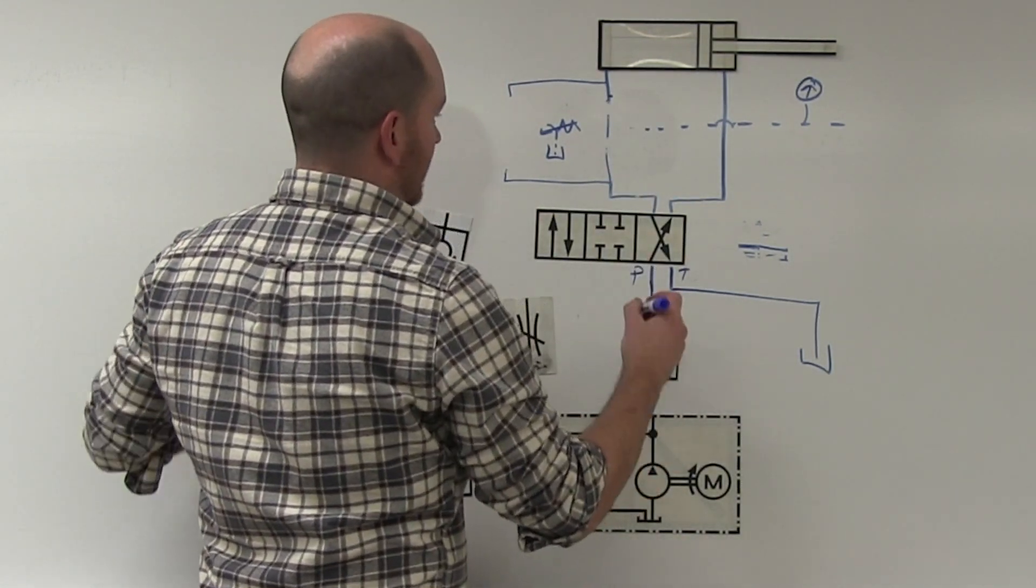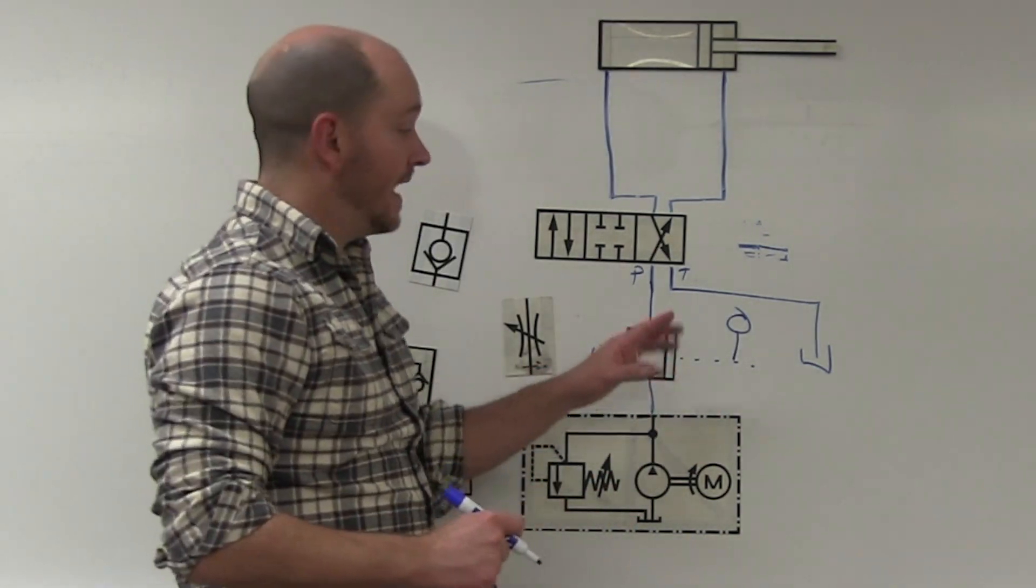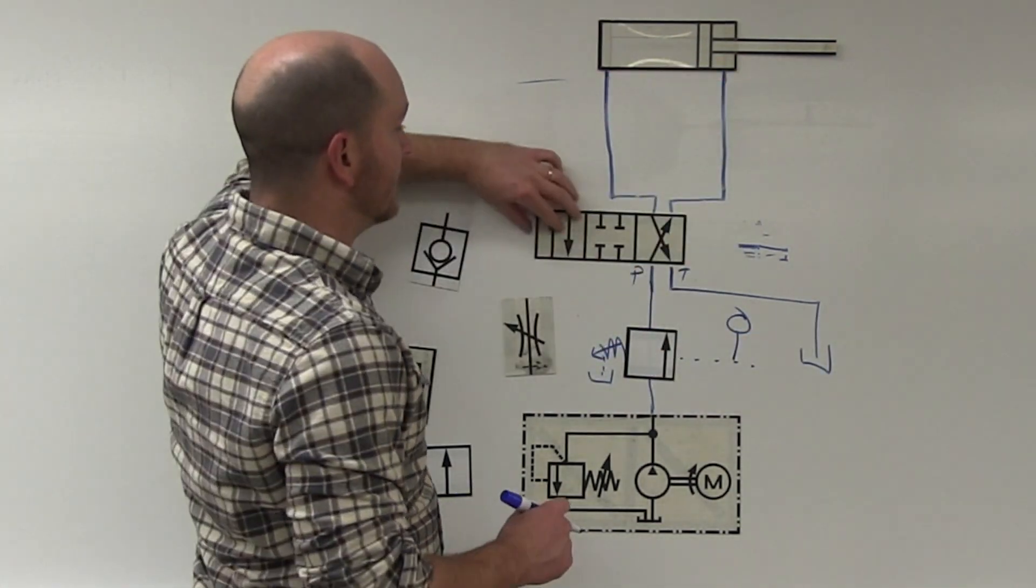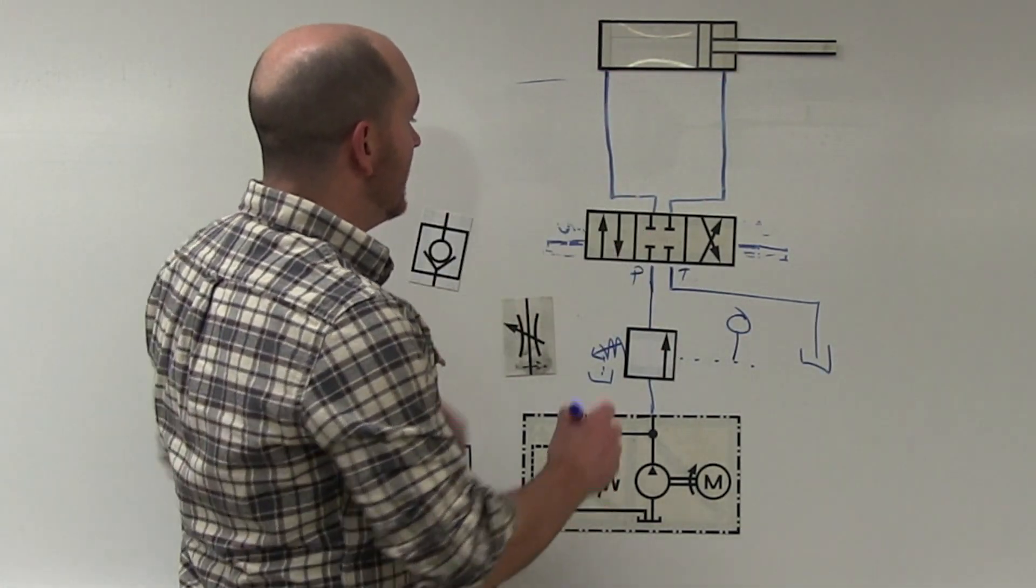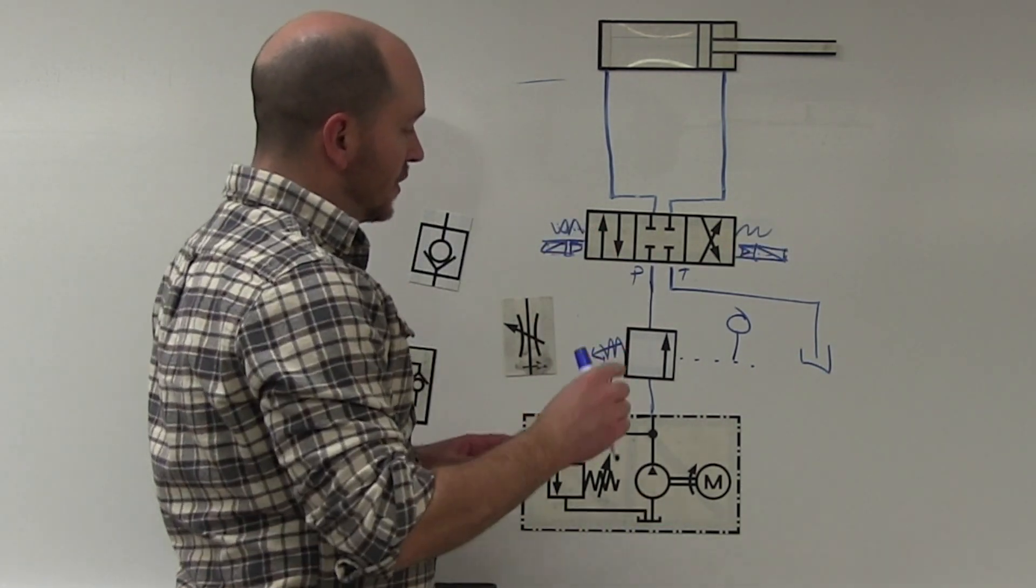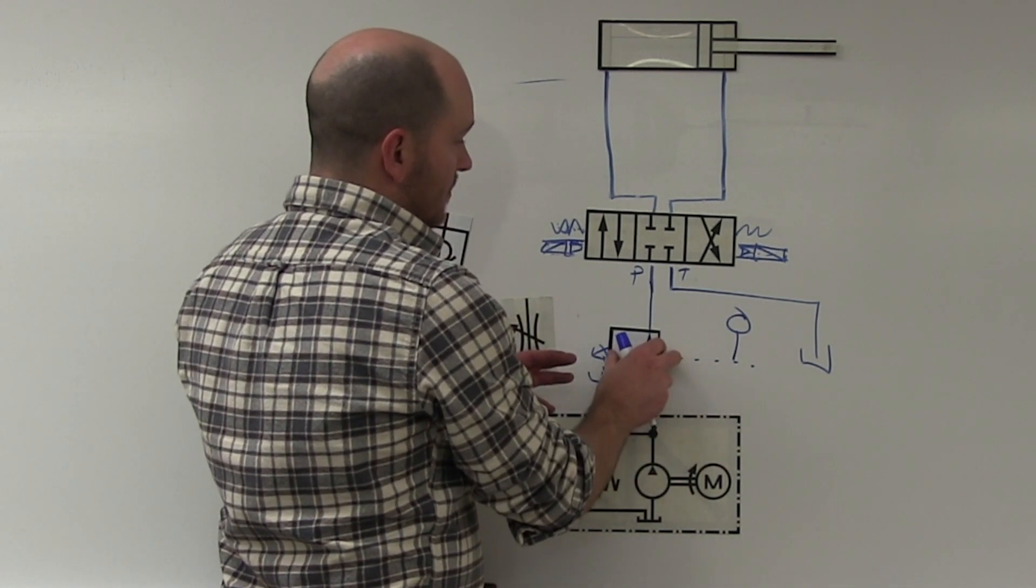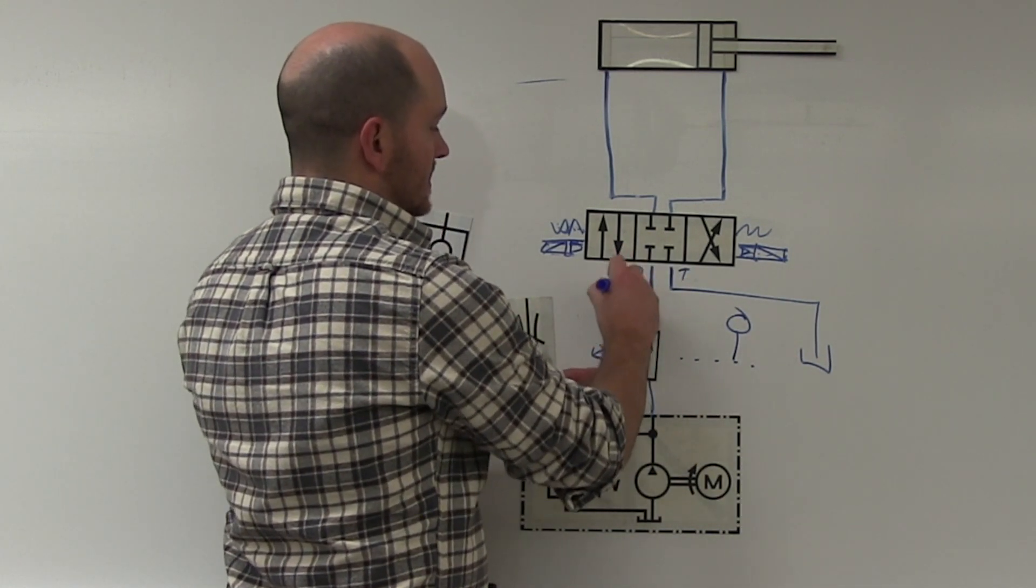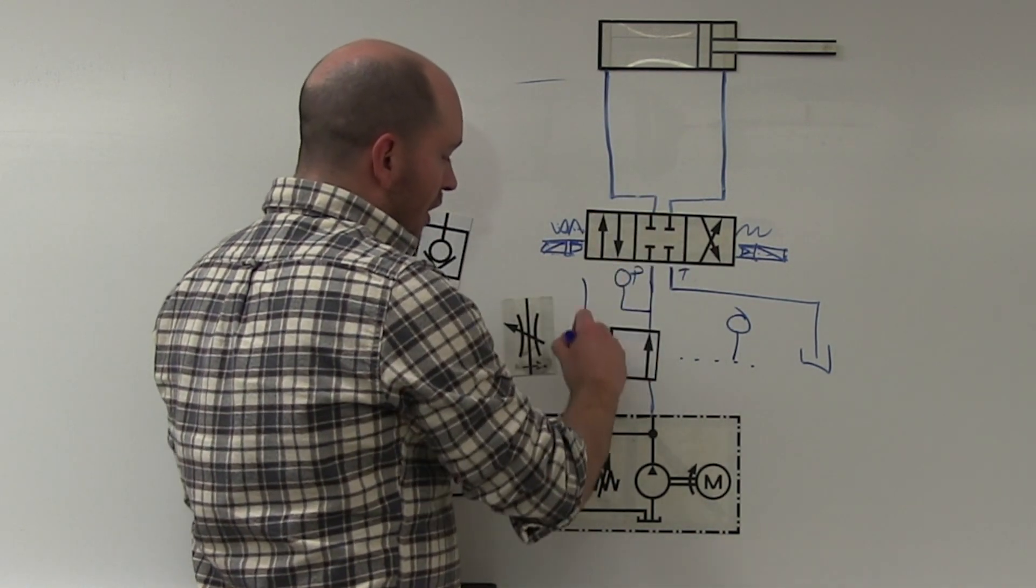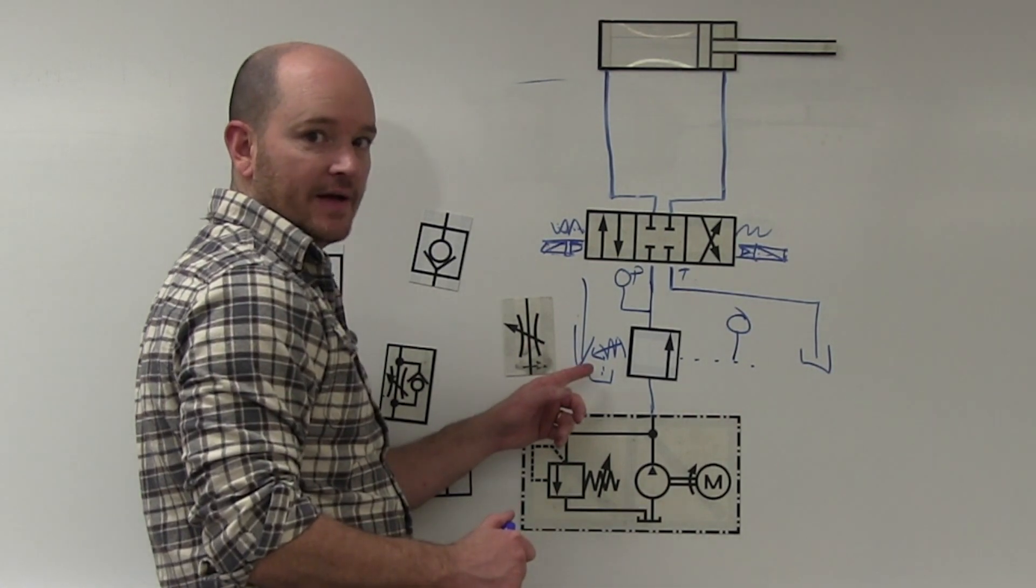But let's say for some reason the system was designed differently. If the sequence valve is down here. Now here, let's say I want to make sure that something on this machine has already happened before this entire device can sequence. This is much different. So now, let's say this gets sequenced over. This moves. Pressure is supplied here. But oil will never go this way. So I don't require a bypass check valve on here.